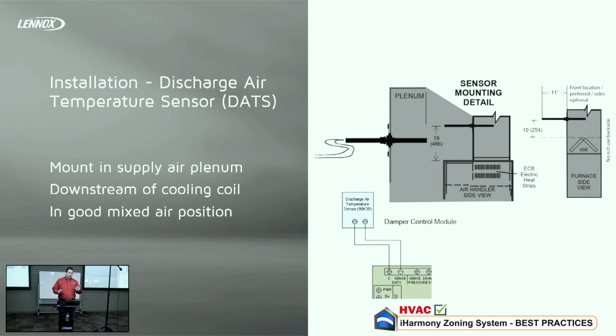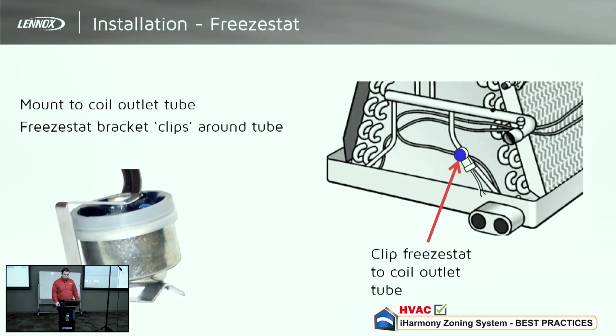So you can put the tip in, use that diagnostic screen to adjust it as necessary, maybe a couple different points. I always tell guys just to adjust it in there and see how that temperature changes, if it changes at all, and find a sweet spot in there, so to speak. So your freeze stat, it's going to clip on the evaporator coil. Yes, sir.